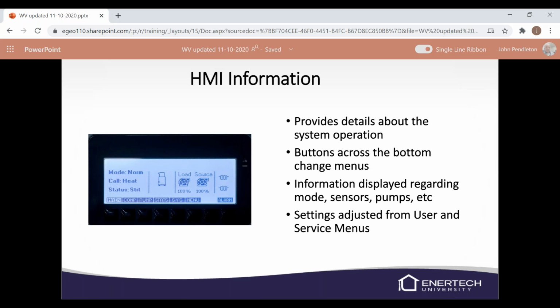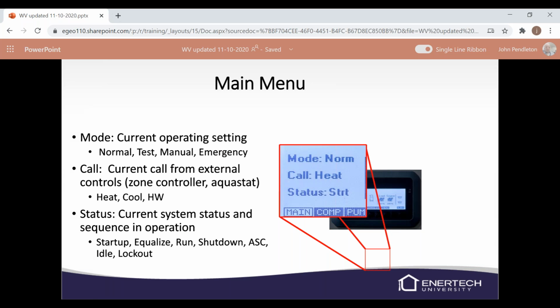HMI, the human machine interface, this is the main screen here. It provides detail about the system operation. There are little black buttons underneath where it says main, comp, pump, status, system, and menu, and also alarm. And you can press those buttons and it'll take you to those different screens. On the main menu, it'll show your mode, which is either normal, test, manual, or emergency mode. It'll list your call, whether there's heat, cool, hot water, or none. The current status. So here it says STRT, which is the startup mode, but we also have equalize, run, shutdown, ASC, idle, and lockout.